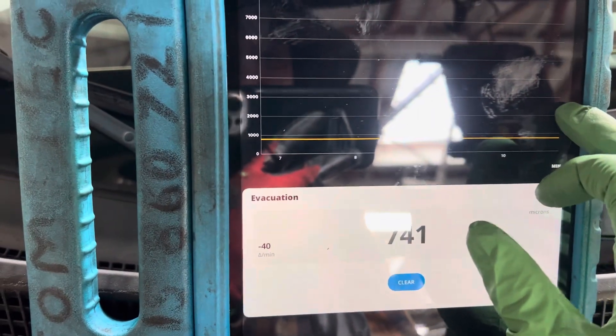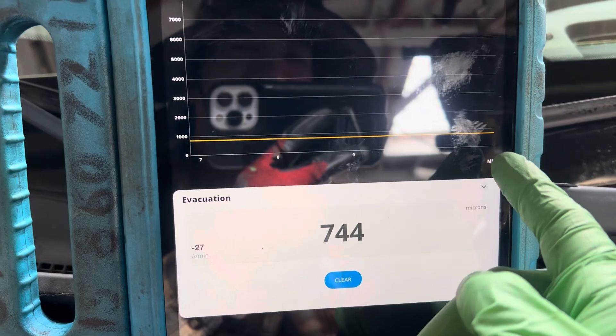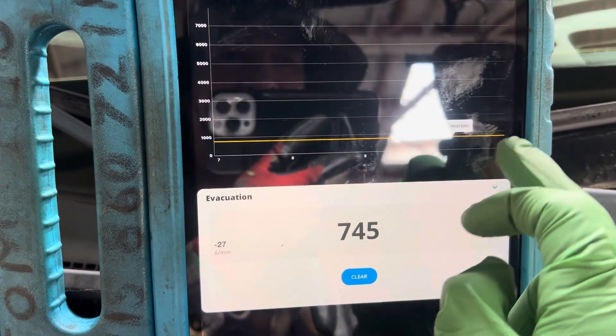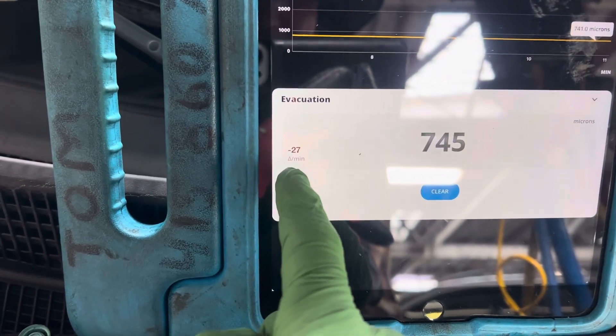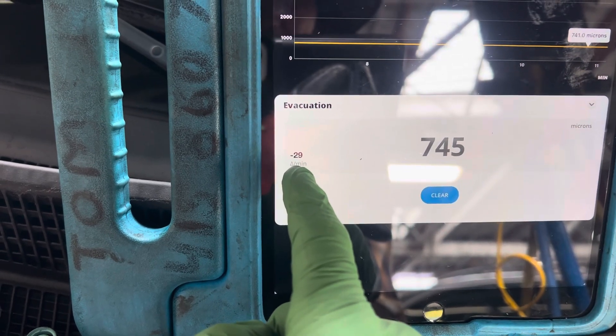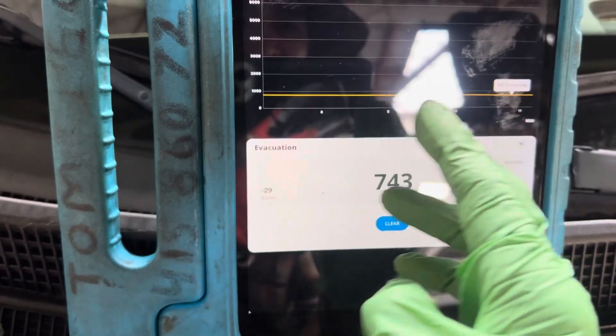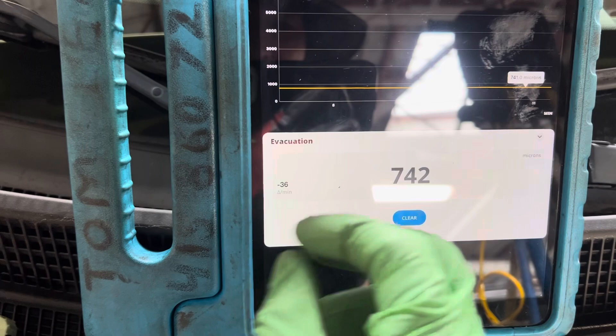Going back to minute 4, it bounces back, but we're going into minute 11 and it's just barely changing — very little drop per minute. In one minute, this delta shows we're dropping like 29 microns in a whole entire minute. As you go farther in time and get deeper, this number will usually get smaller and smaller — you drop less and less.